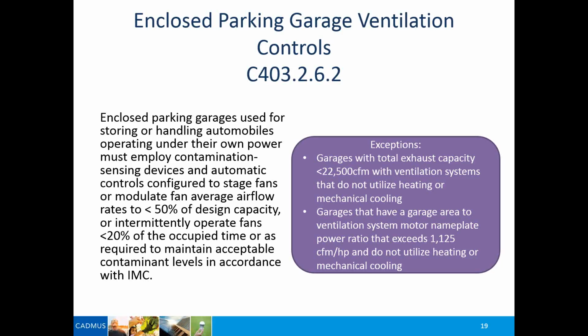So you could have a CO sensor up there to basically say, when it hits a certain level, it actually stages the way the ventilation fans kick on. So you could actually stage it, you can modulate it however you wanted to do it. But the key thing here is that if you don't need 100% ventilation air into that space, there's no reason to provide that, as long as the environment is healthy for the people that are occupying and walking around that parking garage.